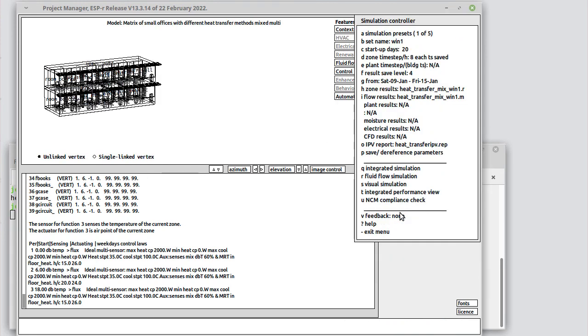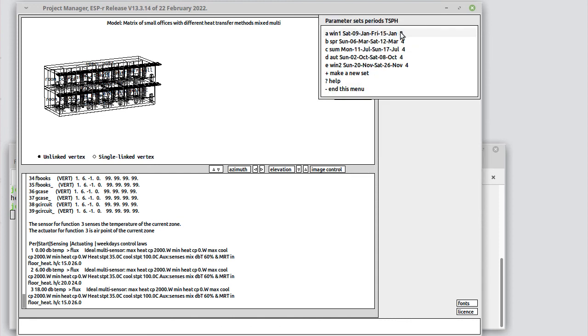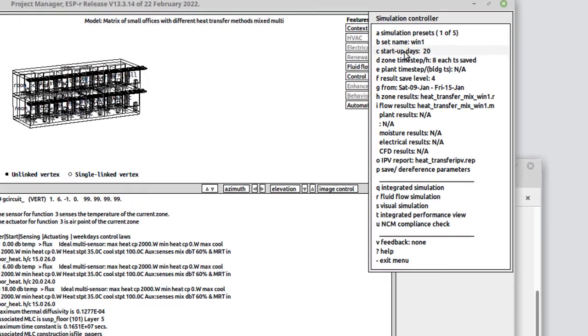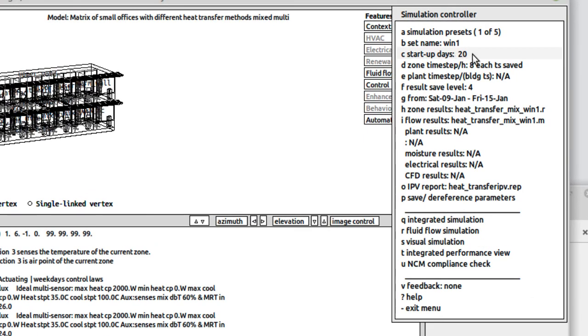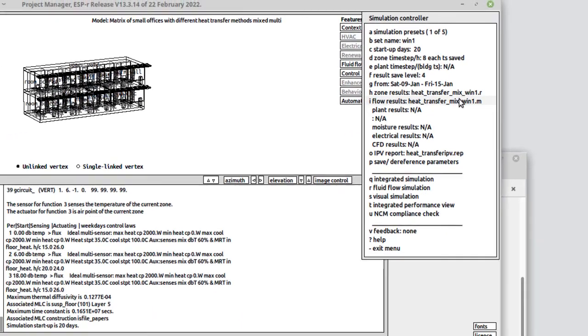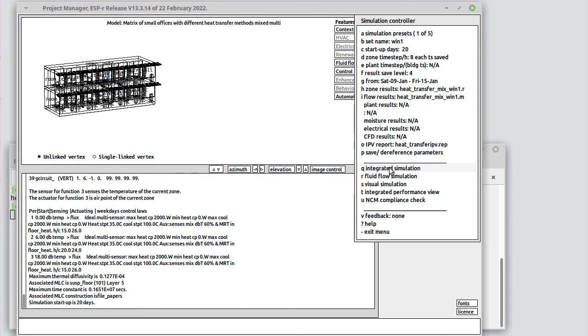Let's run a simulation. We have a number of simulation presets already done. Let's go ahead and see how this behaves with a winter simulation. So it will run for 20 days to get the temperature normalized. It will then run at eight time steps per hour, save full energy balance at the zones and the surfaces, and it will dump out one file for the building results and another one for the mass flow results.